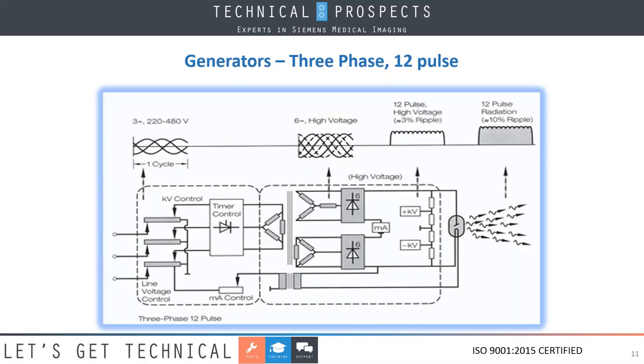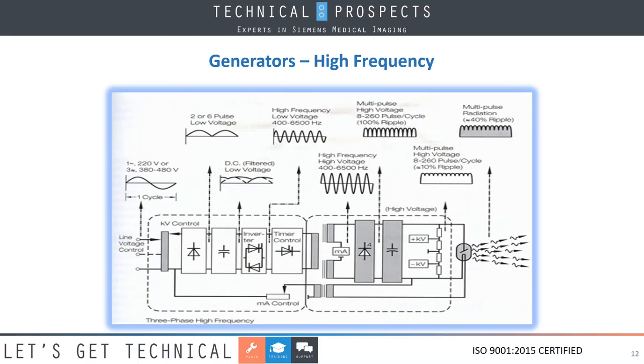Moving on from this one here, we now see high frequency generators. Most high frequency generators here use some sort of configuration that is very similar to this. The biggest thing that you'll see is the big change on the primary side, because in addition to the timer control that's going to the primary high tension on the left-hand side of your circuit, you see we have a diode there that's going to rectify our AC voltage coming in. We charge up a capacitor here that gets applied to our inverter, in which case we set the frequency, which is typically between 4 and 8K, that gets applied to the primary side of our primary high tension.